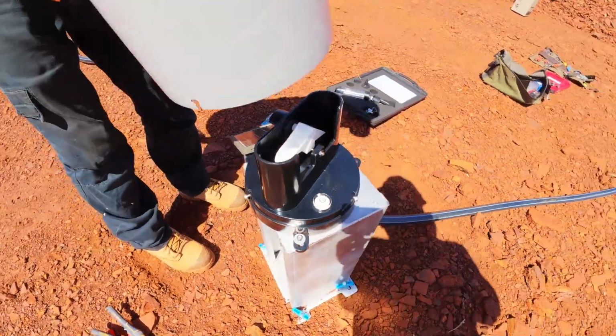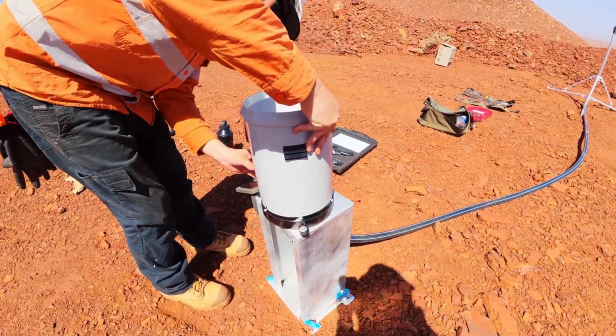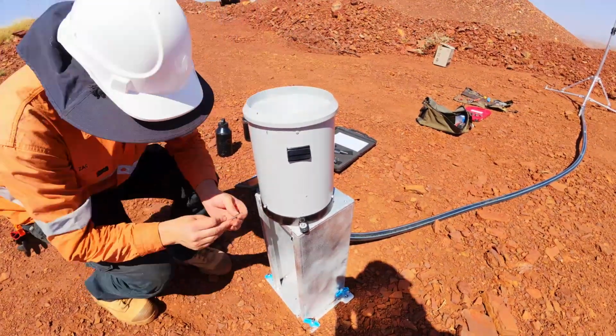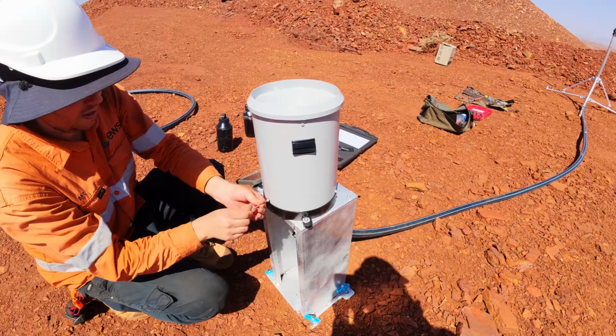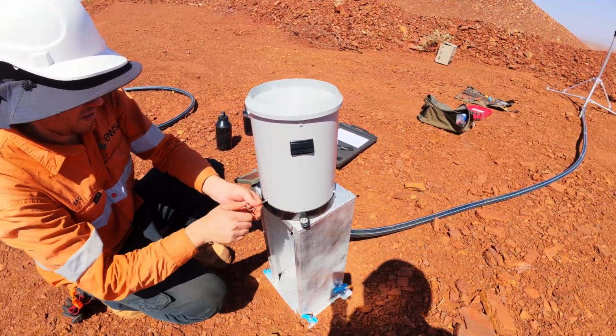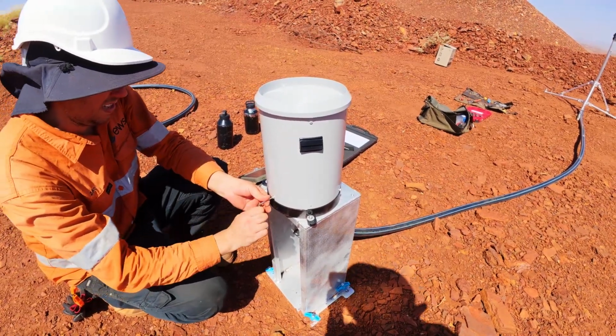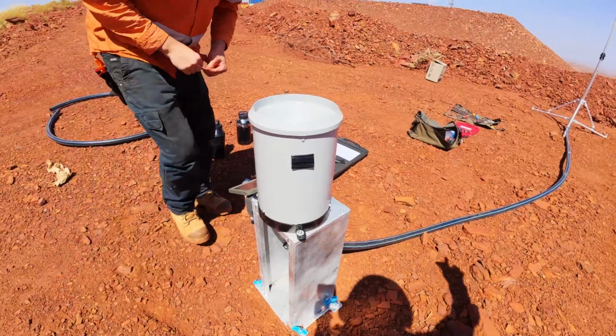Now, make sure to replace the outer cowling of the rain gauge and test the rain gauge using a known volume calibration kit. For this model, we're aiming for approximately 50 tips plus or minus 2 of them. For more detail on rain gauge calibration setup, see our dedicated rain gauge installation video on our YouTube channel.